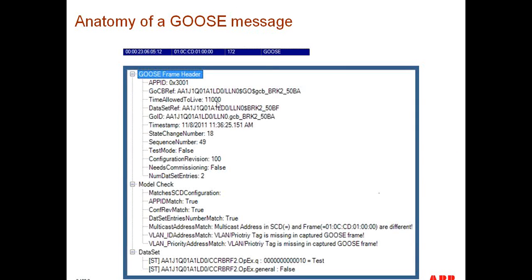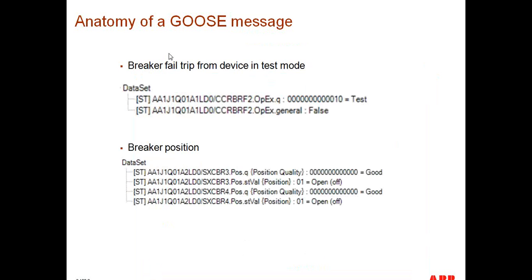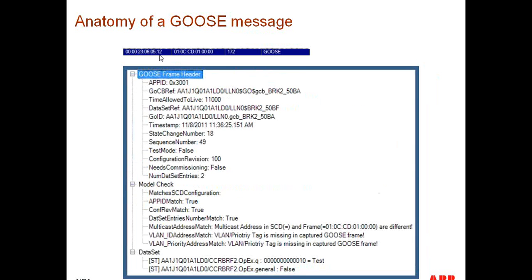If we now look down at the specifics of the Ethernet network, first and foremost, on top, we have the source and destination MAC addresses for this particular Goose message. On the source, we can see that the address starts with 00 00, which means it is the MAC address of a physical device, and it is indeed unique. Then this other MAC address is actually a multicast, and we know it's a multicast because the first octet is 01. This is the destination address of our Goose message.